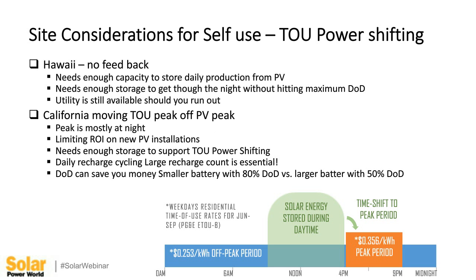Site considerations for self-use: this is time-of-use power shifting. California is switching over to this, and Hawaii has had it for a while now. Some places allow you to feed back, others don't. When selecting your hybrid inverter, make sure you understand what your local utility requires—if they don't allow feedback like Hawaii, you've got to make sure you've got a PV system that handles what you can feed back, what you need to charge, and how you need to support your lifestyle during the day.